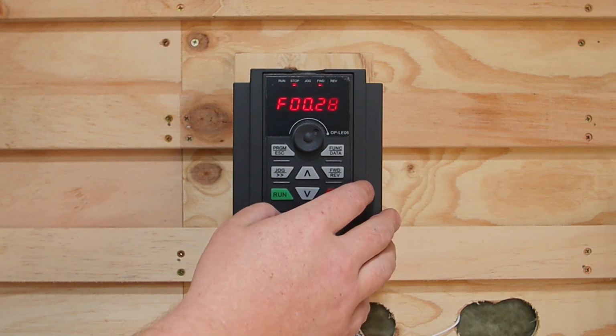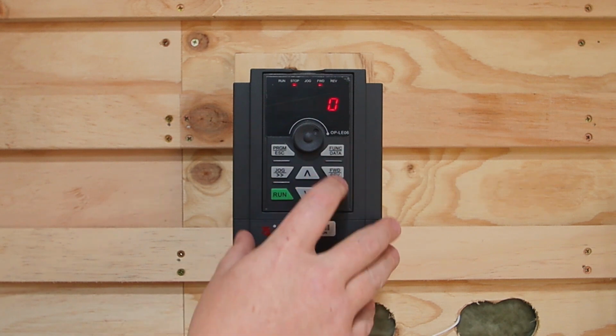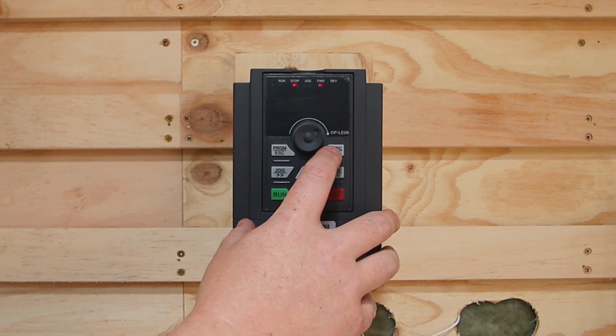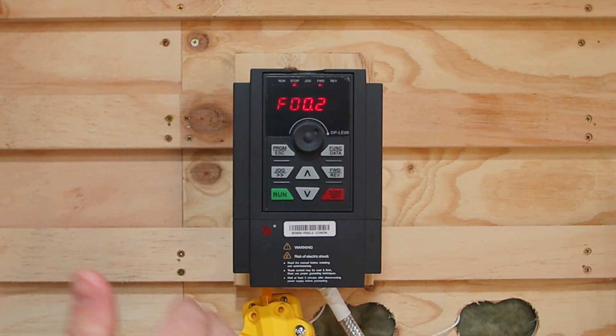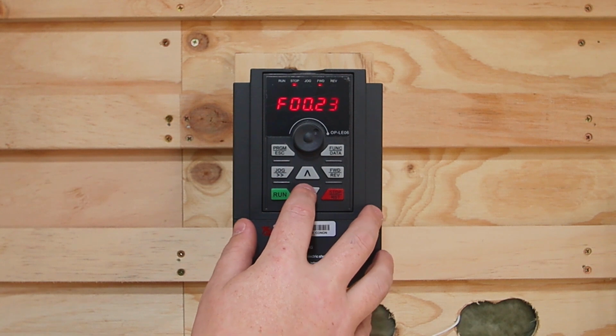Jog down to 0.28, hit function. We're going to go 1, hit function, and that is going to reset this to factory settings. Then we can go through the list of parameters and make sure we have set it correctly by going through each one.